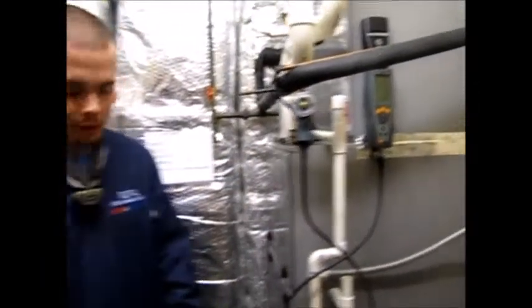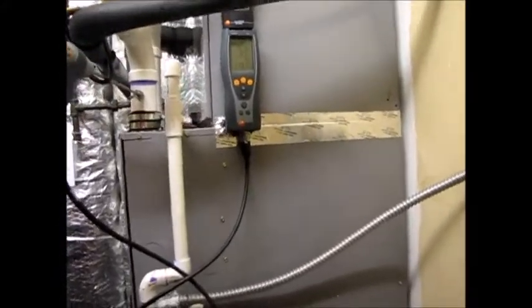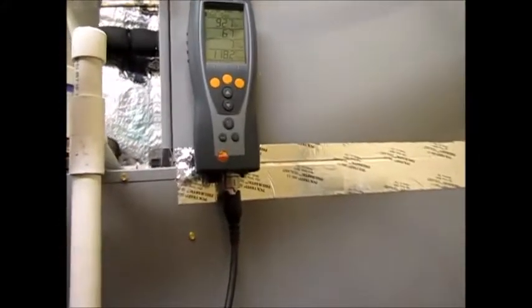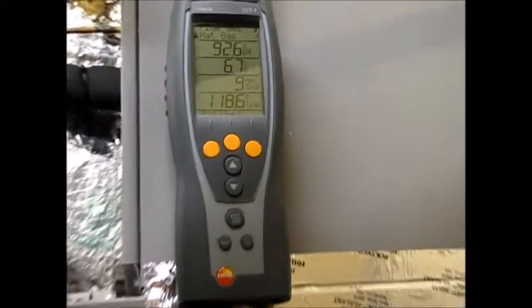If you go back over to our measurements here, you can see that we're doing a lot better on the stack temperature. We're definitely below the 125 degrees, which is what we're looking for on this 90 plus efficiency furnace as far as our stack temp.